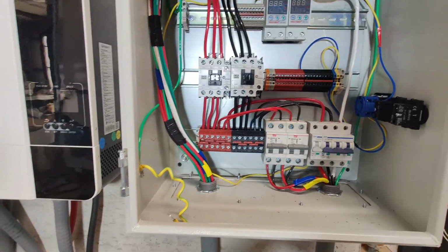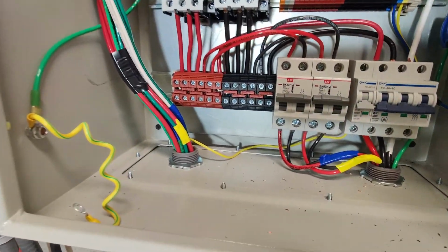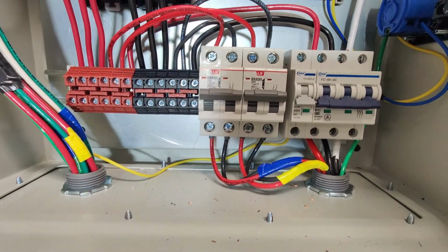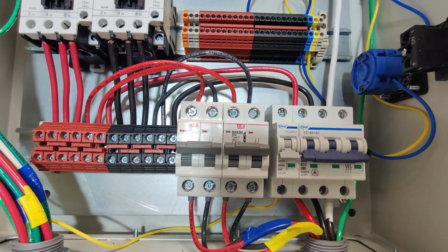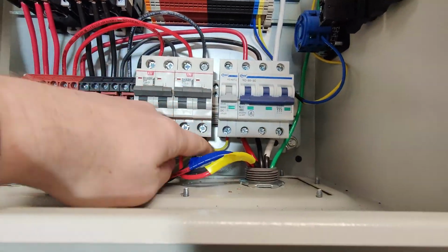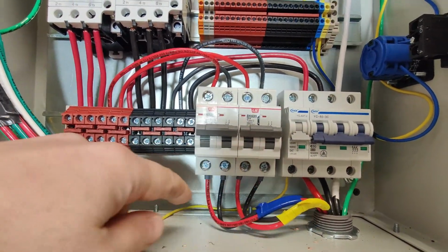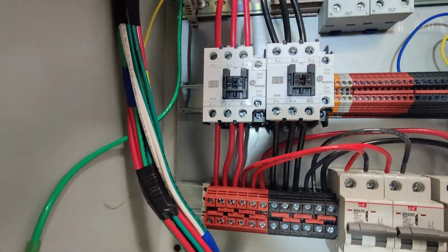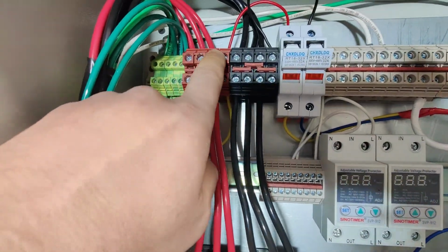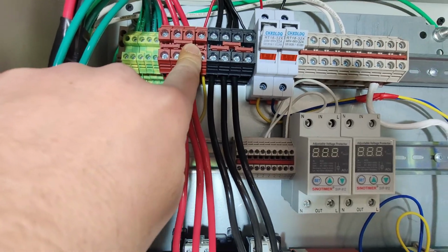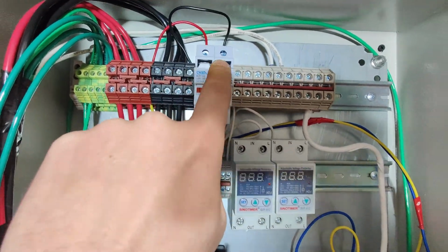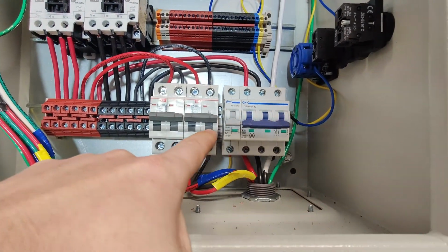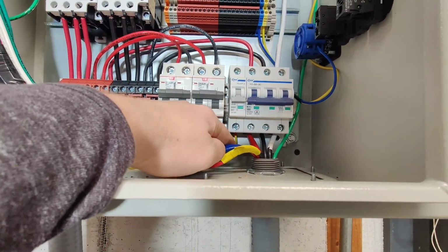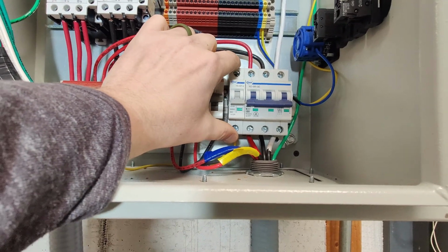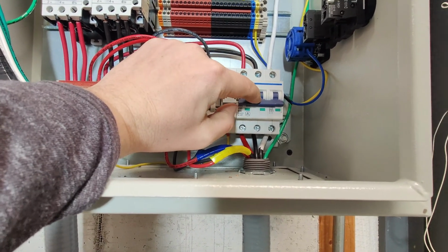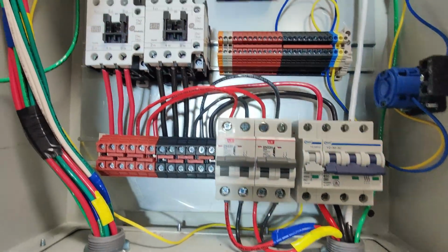So the next thing we've done is we've gone ahead and wired up our shunt trip breaker. And so you see I've got this wire coming in to the bottom side. And this wire here comes all the way over, comes all the way up, and goes directly into one of the hot legs. And there's a reason why I'm not running it through this fuse. So this is an absolute failsafe, that if voltage is applied at both sides of this shunt trip breaker, this thing's going to kill this breaker. And so I don't want to have a fuse in here.